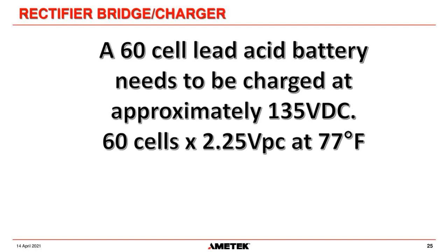So if we went plus 10% on the AC input, then a high voltage on the DC will cause excess water usage. And if we went low at minus 10%, a low voltage will cause sulfation of the plates inside the battery, and both cause battery loss of life. And batteries are expensive and they are a pain to replace. So you want to get as much life out of your batteries as possible.